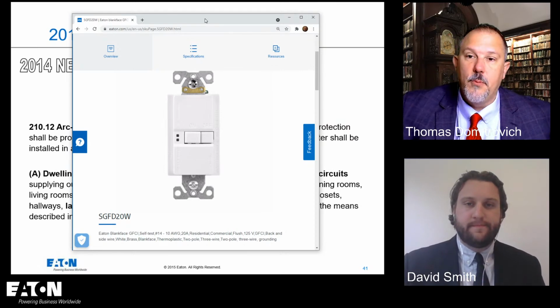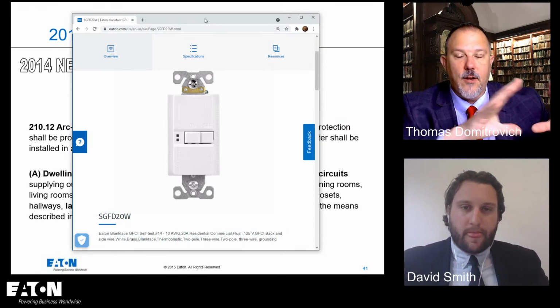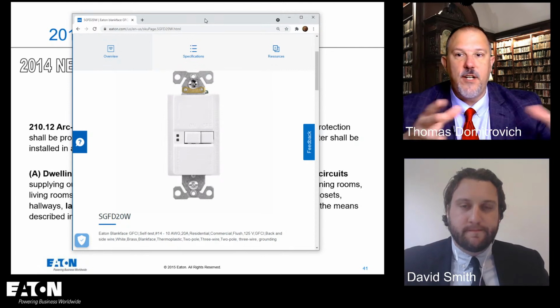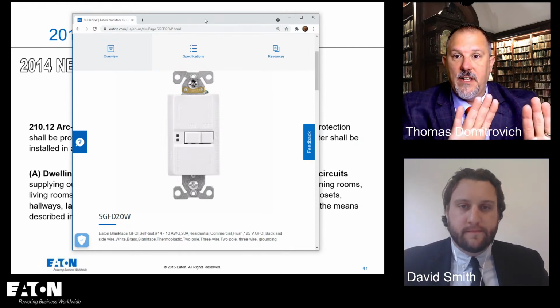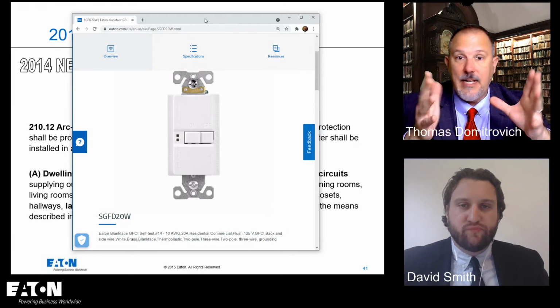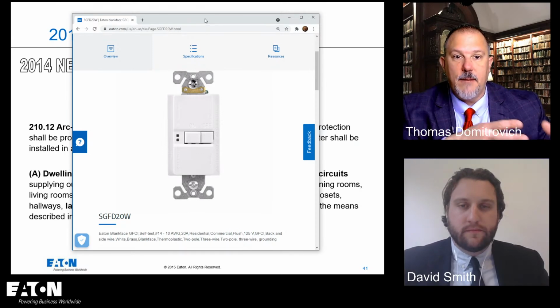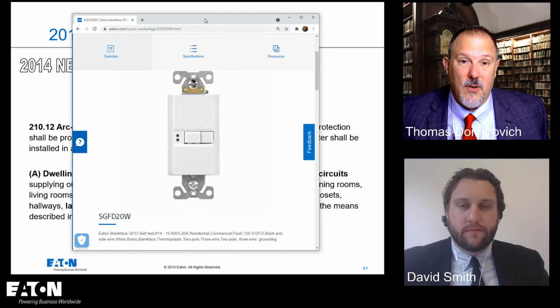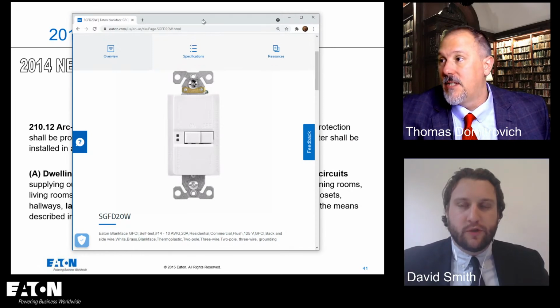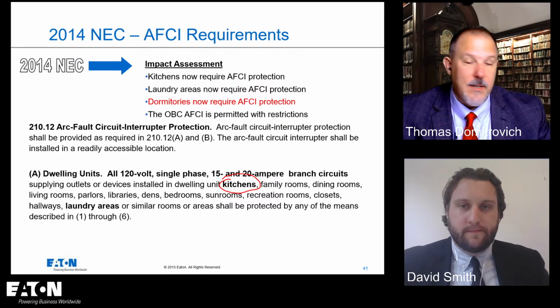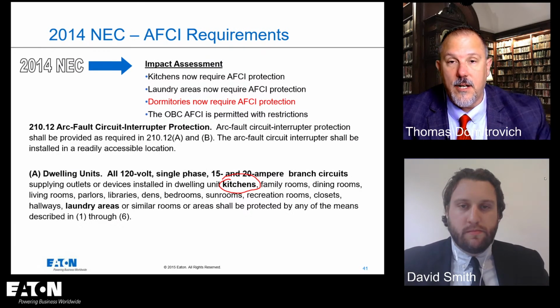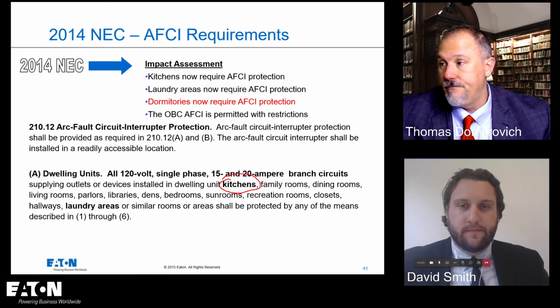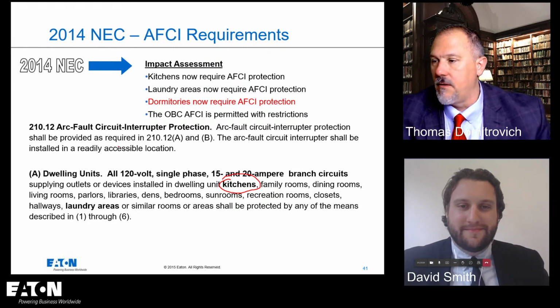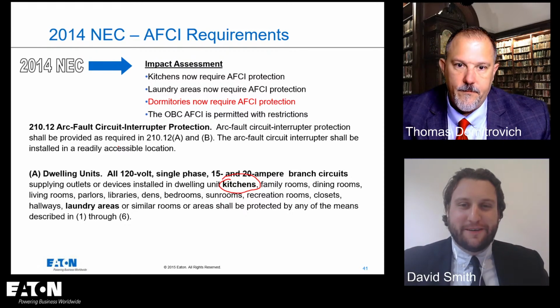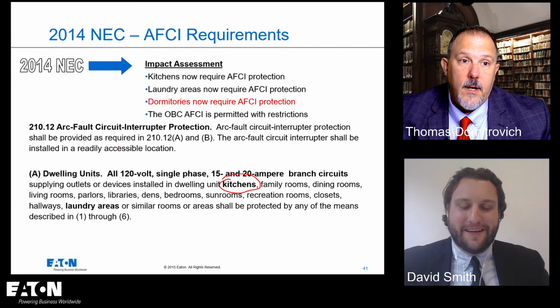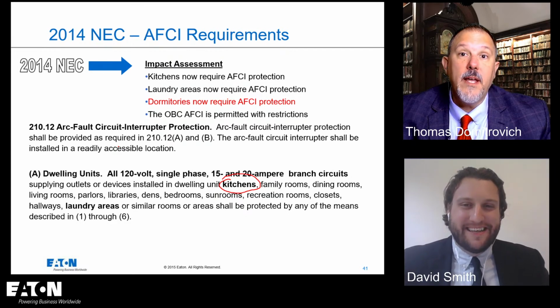And I've seen people put these devices in their basement, and they say, okay, I'm going to put my GFCI protection, these little blank faced items, here where it's easy. They can go find it, so that you're not hunting for the receptacle where the GFCI is. Sure. Because 99% of the time, you've got a circuit that's dead, and then you've got to figure out where the receptacle is, and it's usually behind a piece of furniture. Anyway, sounds like you're making an argument for GFCI or dual function circuit breakers, because it's always going to be in the same place. We make them both.